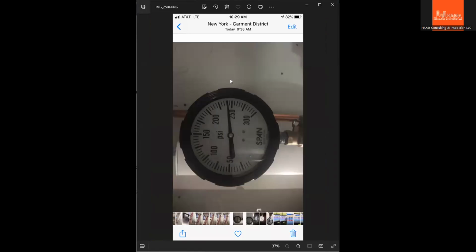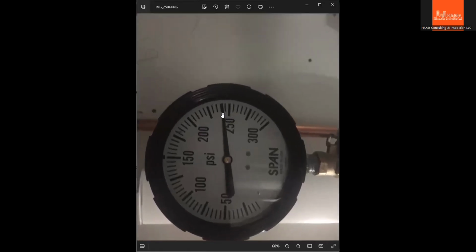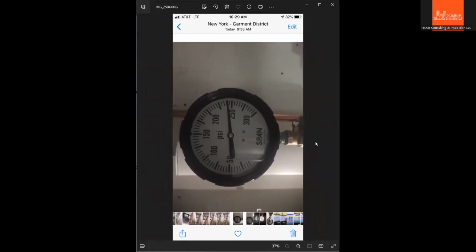So for the pressure that we are using, this is a 2 hour test. I took the photo at 9:38 and then another photo, a screenshot, at 10:29. So the pressure didn't drop at all after an hour. And then at 10:30, still the same pressure. So let me go back to the pressure that we use. This is 200 if it's a steam piping system.